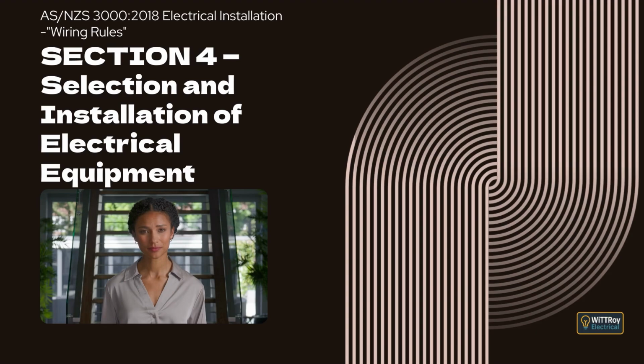Clause 4.18.2.1 Sources of ignition. Electrical equipment that could act as an ignition source must not be installed within the hazardous areas associated with outdoor gas cylinders, except where equipment is approved or not considered an ignition source under the relevant clauses. Clause 4.18.2.2 Hot particles and surfaces. Exclusion zones in hazardous areas for hot particles and surfaces are determined in accordance with Clause 7.7 and AS/NZS 60079.14. Clause 4.18.3 Gas cylinders indoors, New Zealand only.